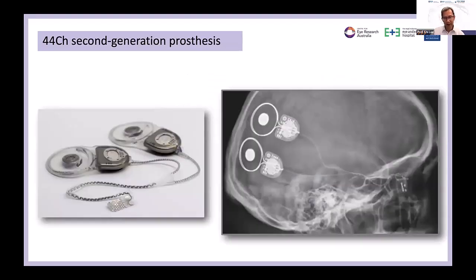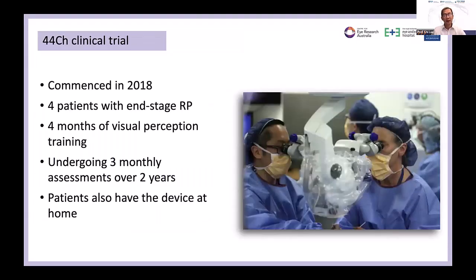So this 44-channel second generation device is powered by two cochlear stimulators, and we need two because each cochlear stimulator only has about 21 or 22 channels, and therefore we need two to power the 44-channel device. So in 2018, we initiated a second trial with this device, and we have recruited 4 patients for this trial. Similar to the previous trial, patients go through implantation, followed by a period of 3 months of recovery and device fitting. Following that, they go through 4 months of visual perception training and continue with 3-monthly assessments over 2 years.